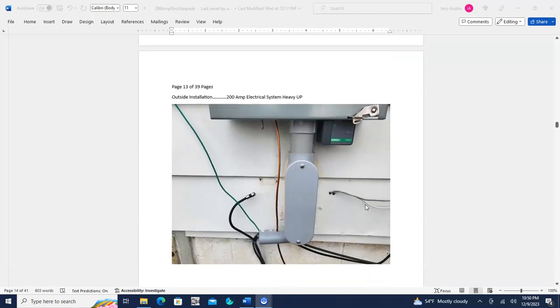And once again, more of the outside installation. This is the ground wire that comes down out of the bottom of the quick disconnect box, which is on the bottom of the meter base. This over here is a surge protector. This right here is an elbow that takes the wires which are inside of this PVC installation down here, and they go through that elbow and they go inside the house.